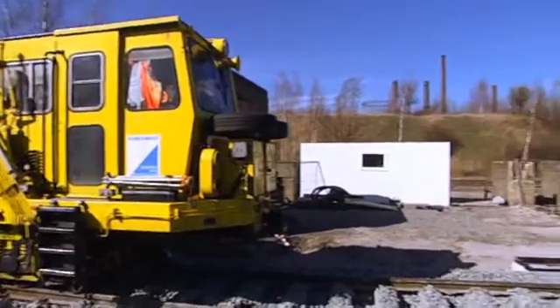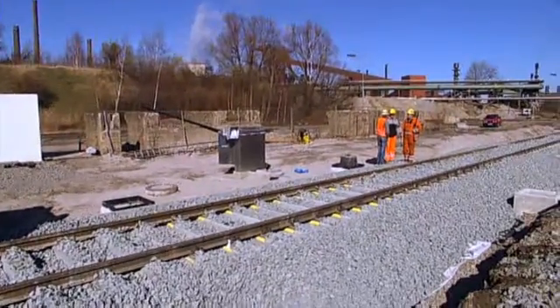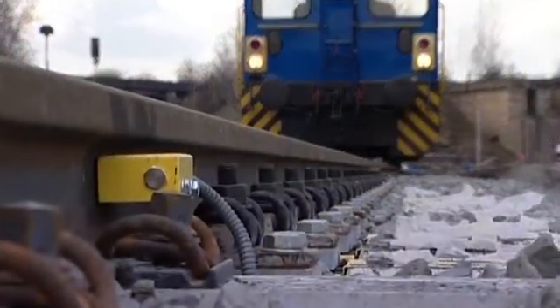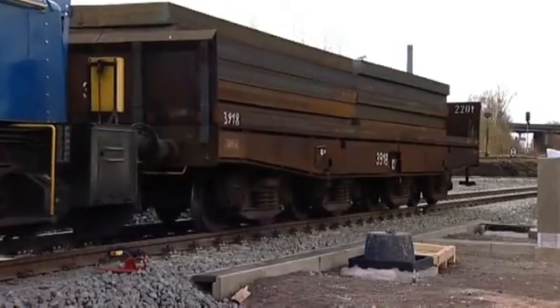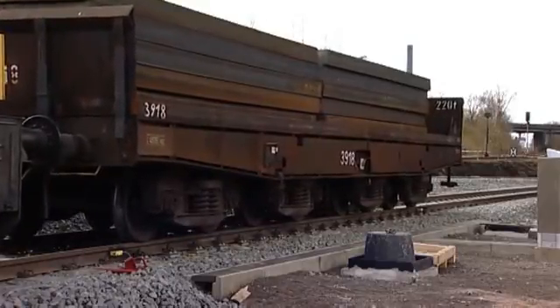Straight after electrical commissioning, a calibration car with a known weight is positioned on the scale to calibrate the weighing system statically. The customer does not need to provide an approved static reference scale for this electrical adjustment, which makes the system very cost effective for the final user.